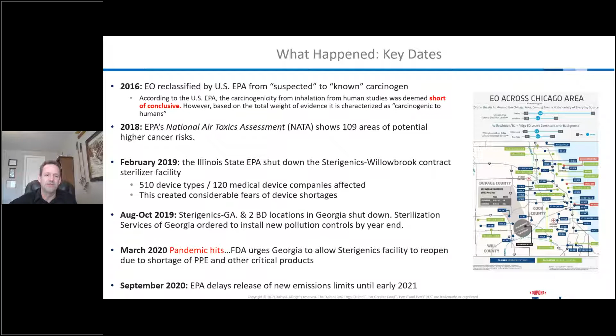When you talk about potential patient safety, the numbers are just enormous. There are over 2 million different medical devices listed in FDA's Global Unique Device ID database, and 40% of all those devices are sterilized. Of all the devices that are sterilized, 50% are sterilized with ethylene oxide and 40% with gamma. Now, this is wide-scale, large sterilization, not what's done in hospitals. Hospital sterilization is a lot different, but you're talking about 90% of all devices that are sterilized on a large scale being affected by some of the issues we're going to talk about.